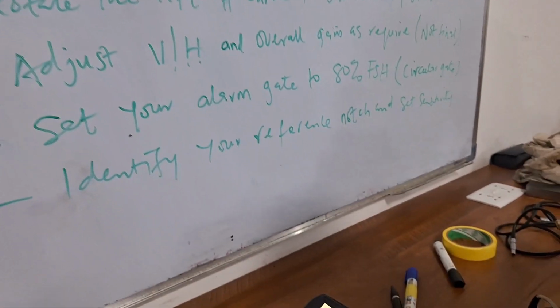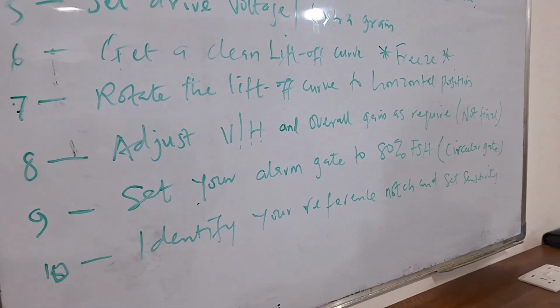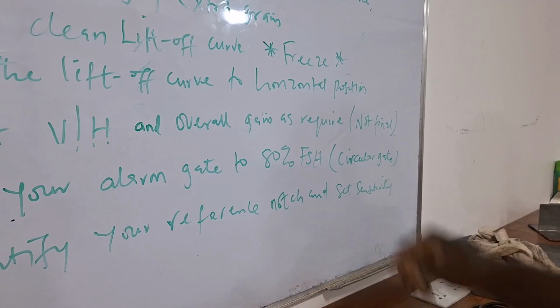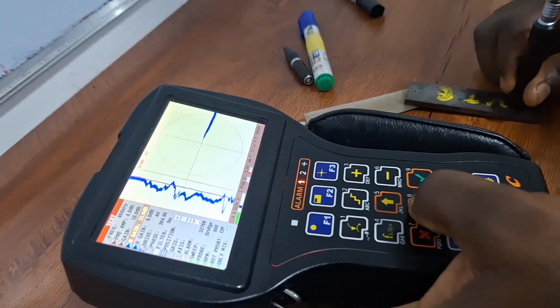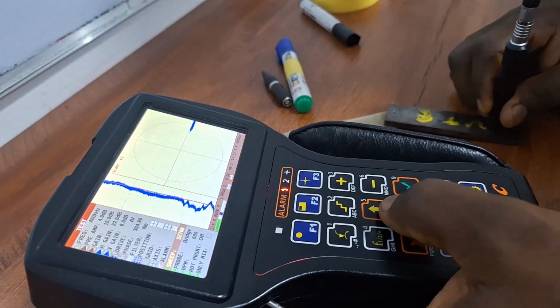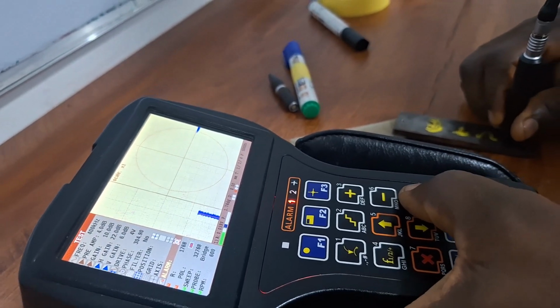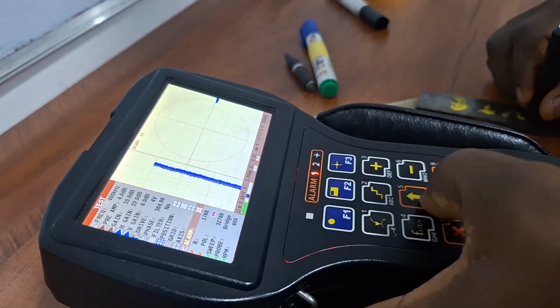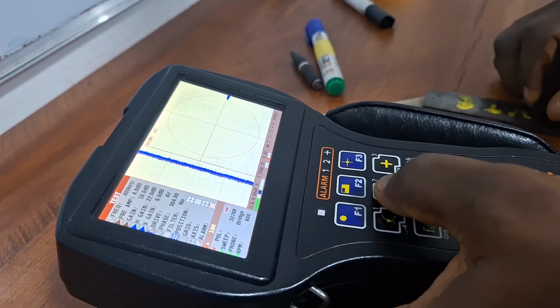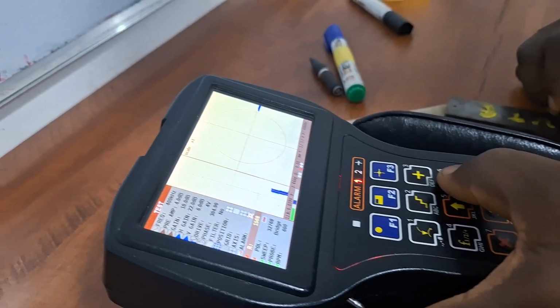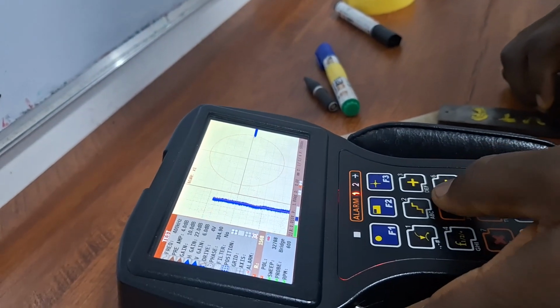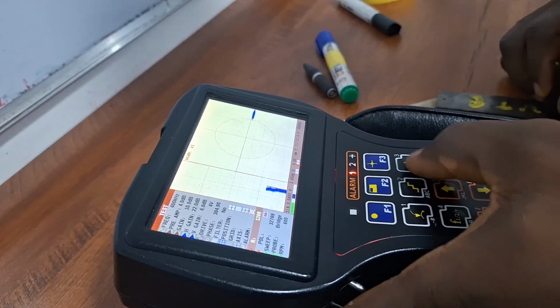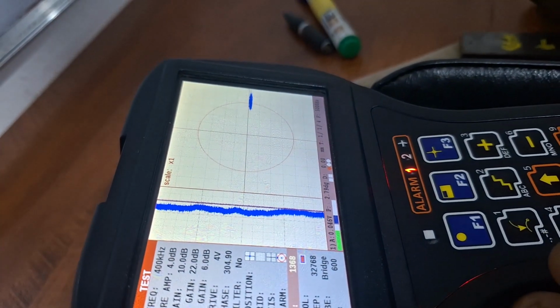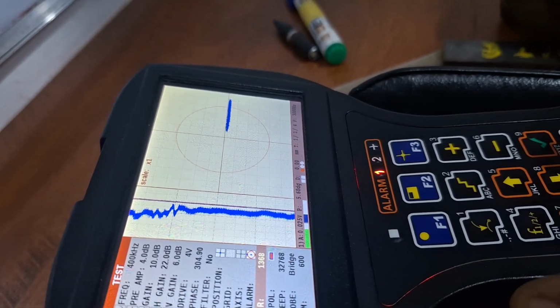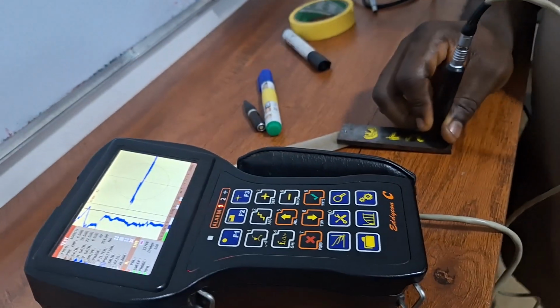So the next thing we'll try to do is to set our alarm gates to 80% of full screen height. Take note, we're always using the circular gate. So if you look at this machine, it's already set up to 80%, but we can adjust as we want. We can go to alarm and we can do fine adjustments on the step. We'll come down and we can step it by say 100 and reduce this until it is almost exactly 80%. So if you look at it, this is 20, 40, 60, 80. So this is exactly at 80%. So that is what we have done.